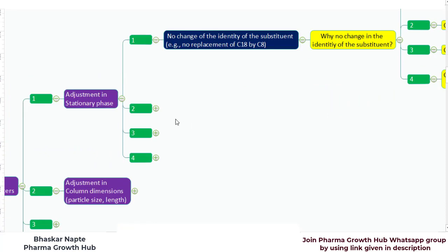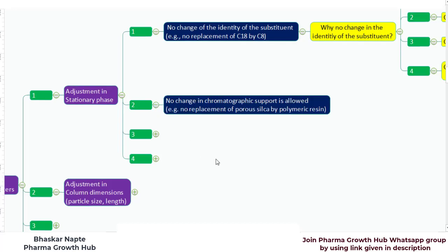When it comes to adjustment in stationary phase, point number 2 is: no change in chromatographic support is allowed. For example, if the monograph column specifies porous silica as the support material, you cannot change the support material to a polymeric resin for any reason.